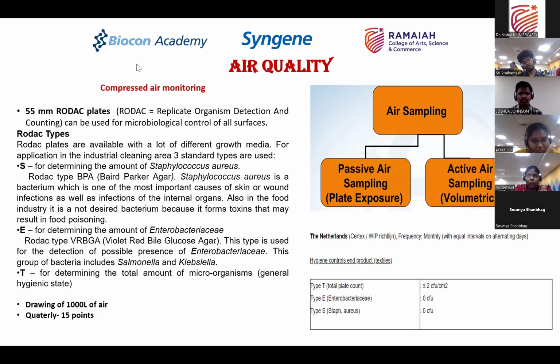Now, what is meant by passive air sampling? We'll be just exposing the plate in an area and allowing the air of that particular area to settle on the plate. This is called the plate exposure method. We are going to use that to count the viable organisms, that is microorganisms. Now, when it comes to active air sampling, what is meant by active air sampling?